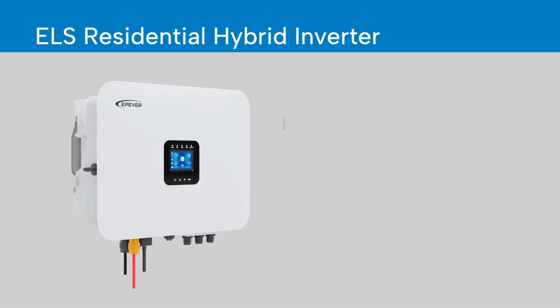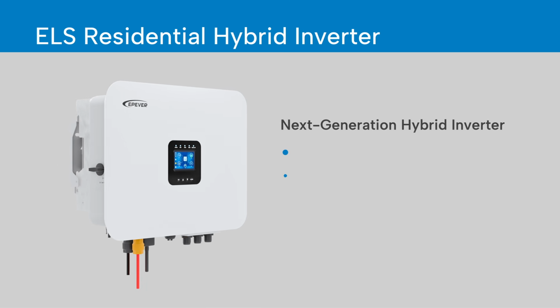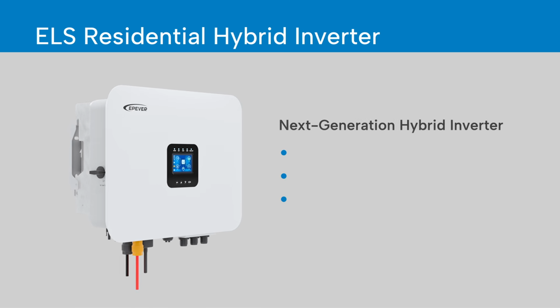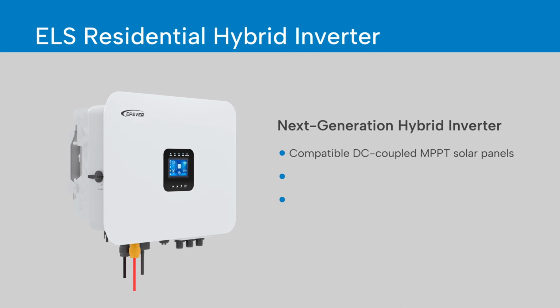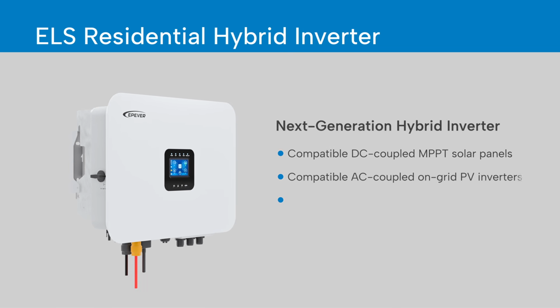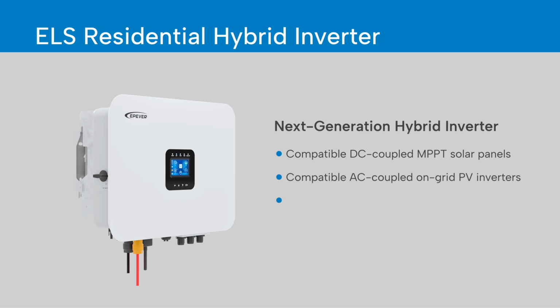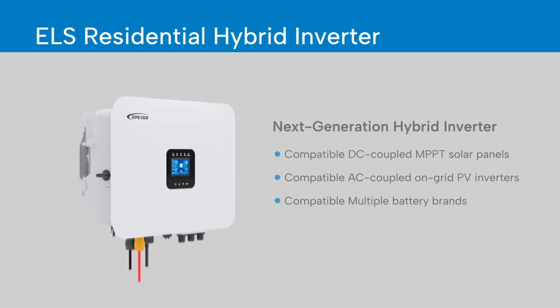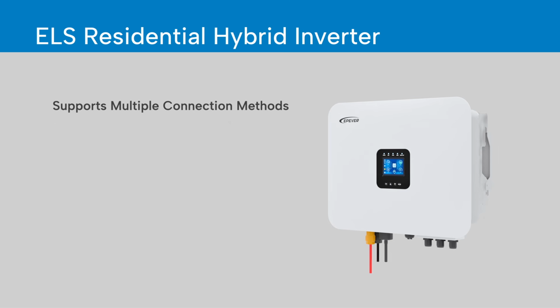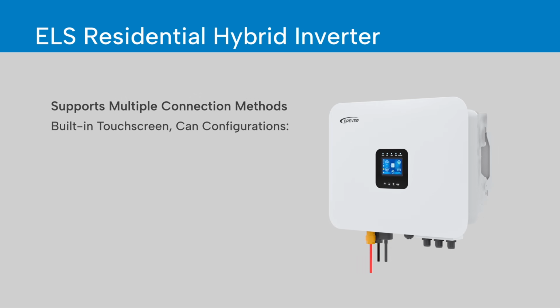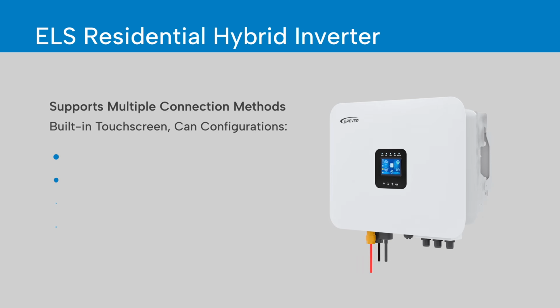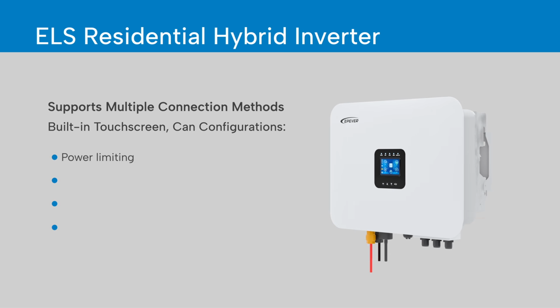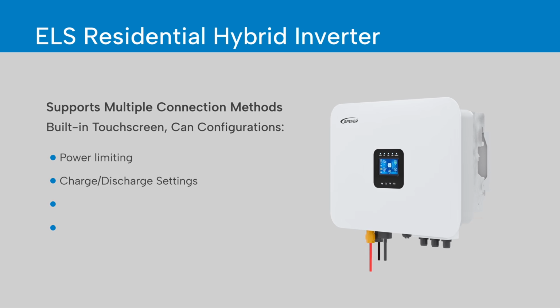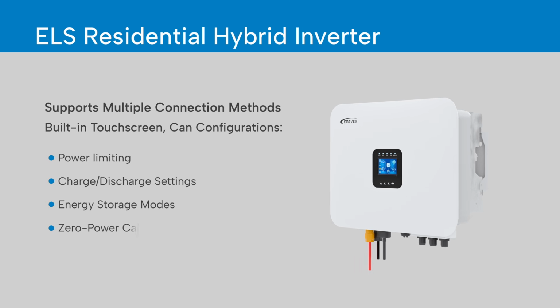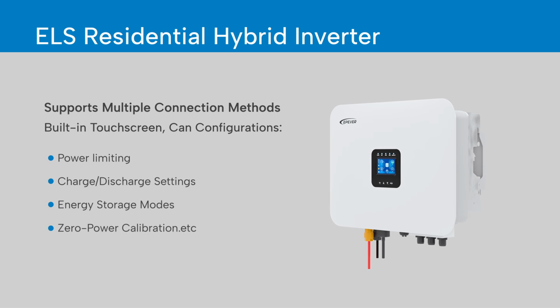The ELS residential hybrid inverter is a next-generation product compatible with DC-coupled MPPT solar panels, AC-coupled grid-tied PV inverters, and multiple battery brands. It supports all the connection methods discussed today and features a built-in color touchscreen. Most system configurations, such as power limiting, charge-discharge settings, energy storage modes, and zero power calibration, can be adjusted directly on the screen without a laptop.